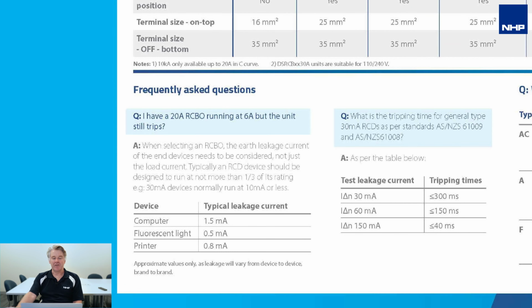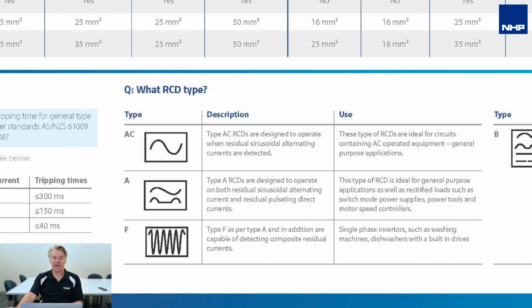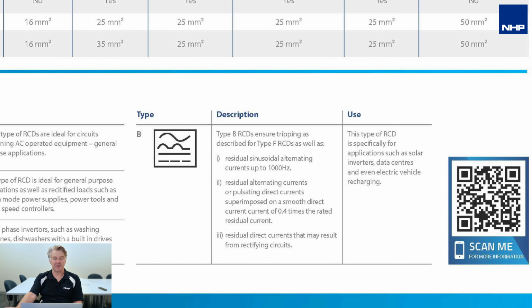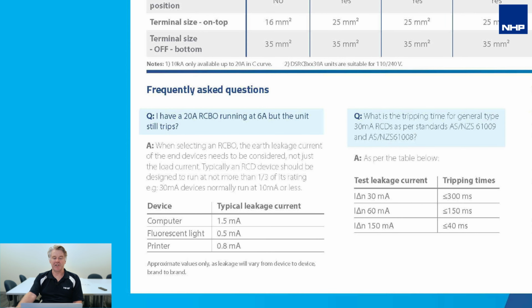There's also some frequently asked questions along the bottom here to help in the guide of selecting RCDs. There's a definition of the type AC, type A, type F and type B that you can see across the bottom, as well as typical leakage currents. It's always recommended that the nominal leakage current of your RCD is 1/3 of the sensitivity of the device. So if it was a 30mA device, it should nominally not be greater than 10mA. For 10mA, it should not nominally be greater than 3mA as a guide of reference to avoid nuisance tripping.